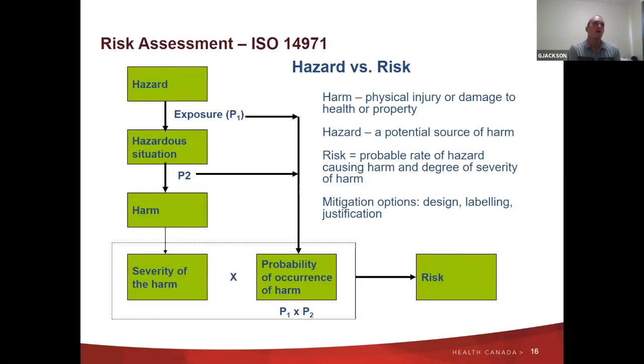A risk assessment is required for a class 4 device. It's not always required for a class 3 device—sometimes we will ask for it, but it can be useful for it to just be provided. ISO 14971 is a common standard for medical device risks, where the manufacturer looks at what hazards exist, what situations bring them about, and the harm based on severity and probability of occurrence. They then put in mitigations for each hazard and verify proof that they've mitigated those to as low a level as possible, or show that the remaining risk is outweighed by the benefit of the device. This depends a lot on what the device does, what it is, and what the remaining risks are.